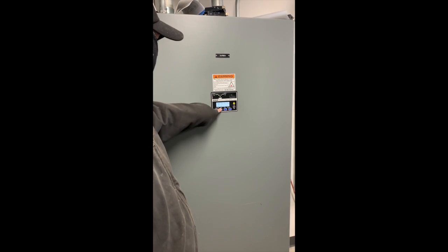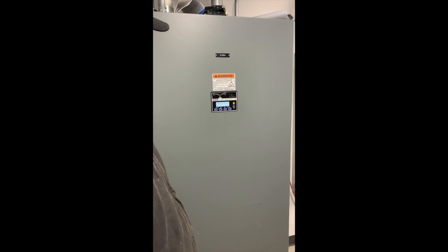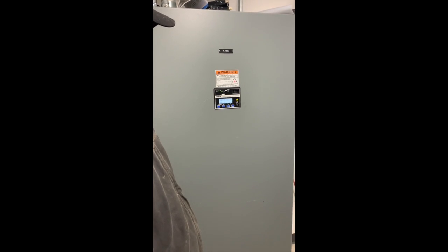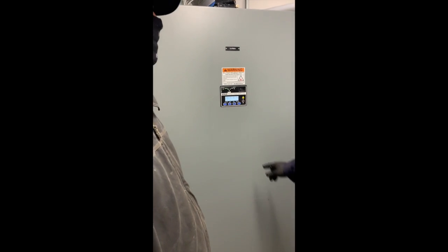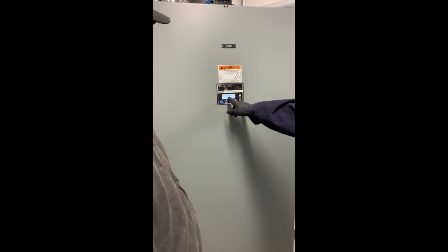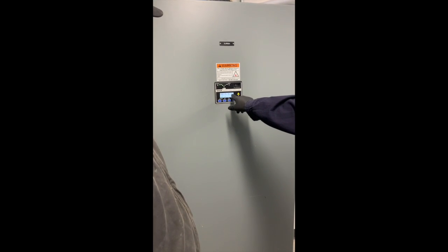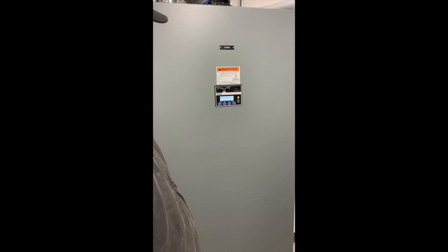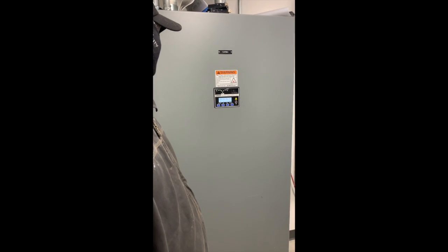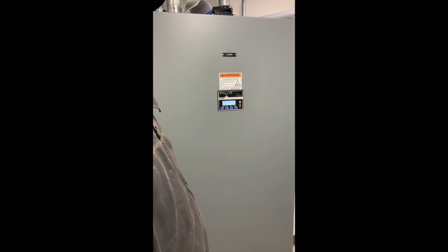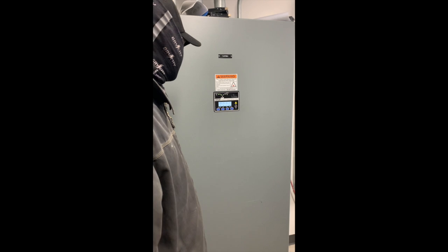Wait, could you go back to that one? There's quite a bit of disparity on that PG&E side. This is okay, but that's pretty high on the third leg. I mean, that's got nothing to do with this. That's from the legs coming in from PG&E. That's normal source side.